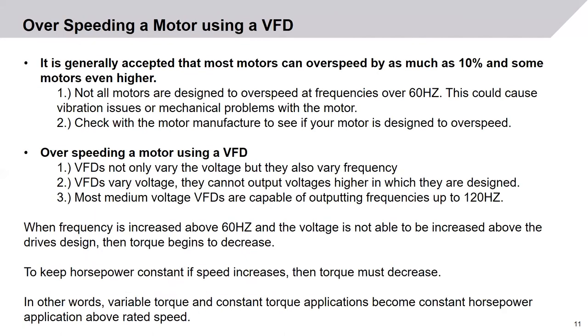It is generally accepted that most motors can overspeed by as much as 10% and sometimes even higher. Not all motors are designed for overspeed, so you should speak with your manufacturer to confirm. VFDs not only vary voltage, but they vary frequency. They cannot vary voltage higher than what they were designed for. Most medium voltage variable frequency drives are capable of outputting frequencies up to 120 hertz. When frequency is increased above 60 hertz, the voltage cannot be increased above the drive's design, and torque begins to decrease. To keep horsepower constant, if speed increases, torque must decrease. In other words, variable torque and constant torque applications become constant horsepower applications above rated speed.